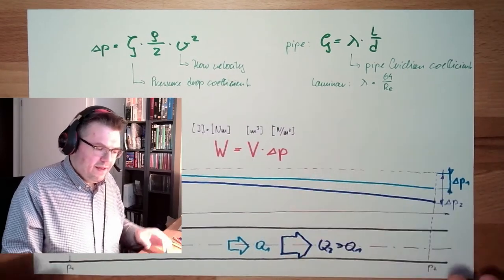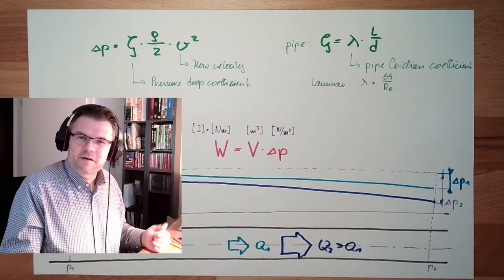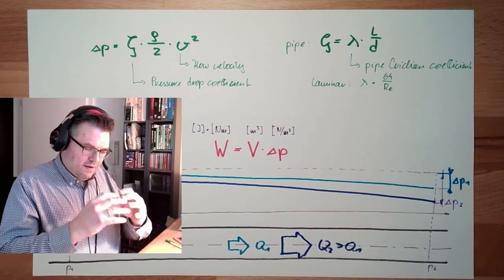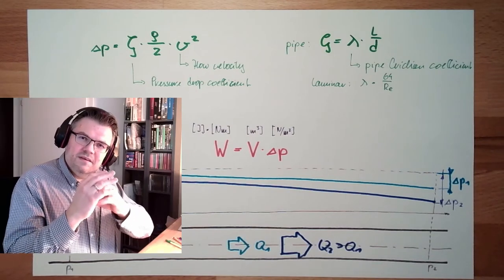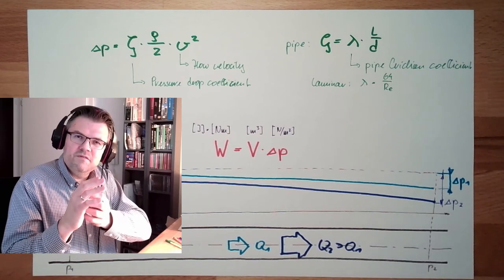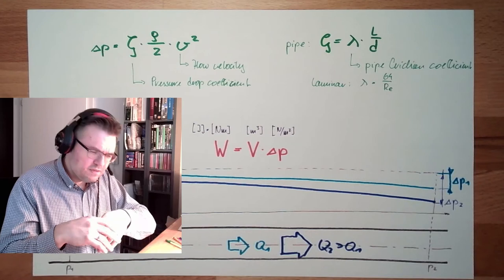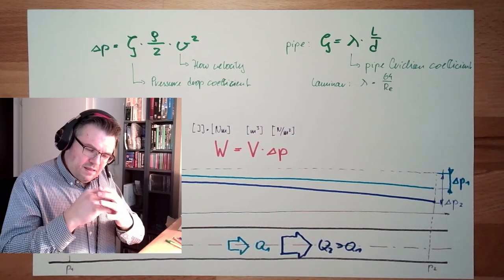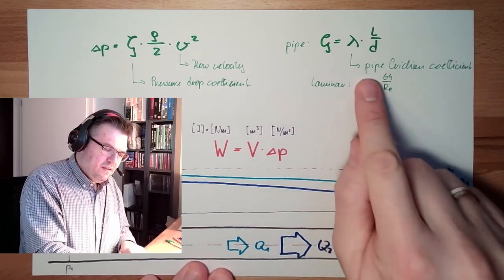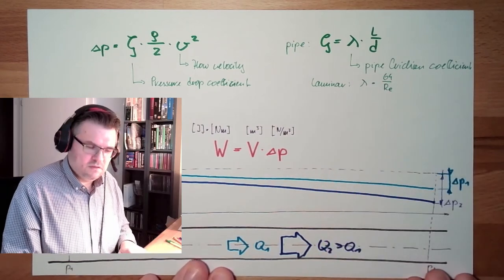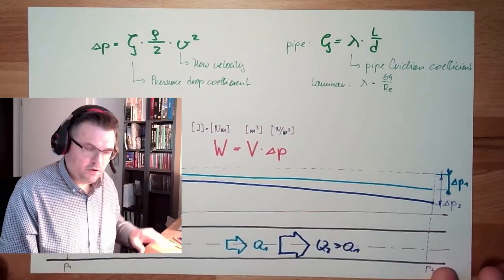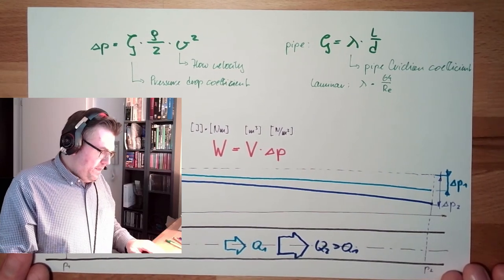And if it's turbulent, you have to go into a diagram. And then it strongly depends on the roughness of the surface. If it's a very smooth surface inside the tube, or if it's rough, if it's concrete, or if it's metal, or if it's rubber. This depends on the roughness or smoothness of the surface inside. And this gives them different lambda values, resulting then in a pressure drop. This is for pipes.